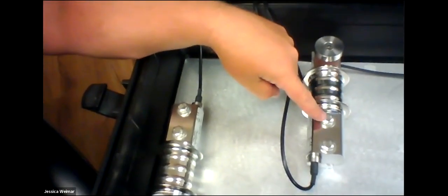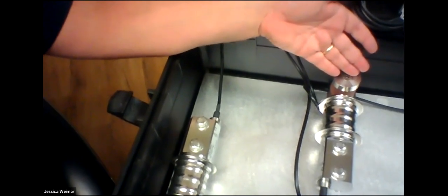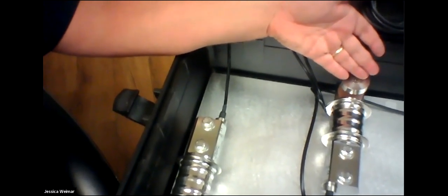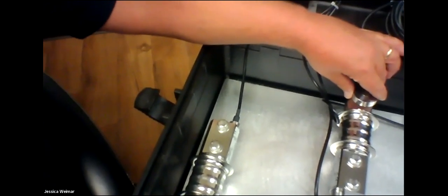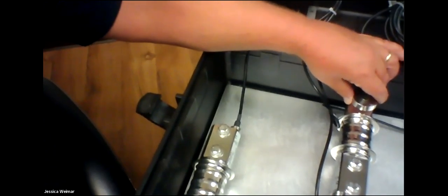But take a look here, and you can see that the cell itself is bolted down to a mounting block that would be welded to the frame. This is the mounting kit that would be welded to the bottom of your live load, and that's all that's required. You don't need any other equipment. This kit has a flexible mounting bushing on it that allows the unit to be slightly out of alignment and still maintain accuracy. So even with side loads or shock loads, this unit is capable of handling that without any concern. I hope you could see that, and I think somebody's asking me a question.